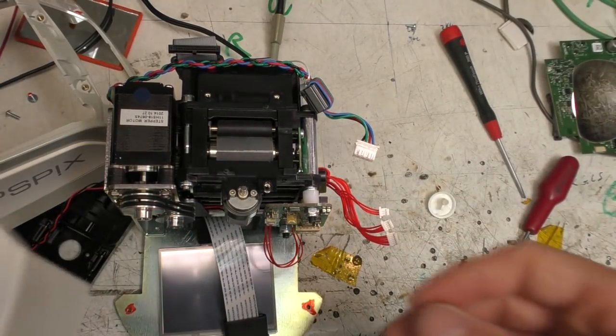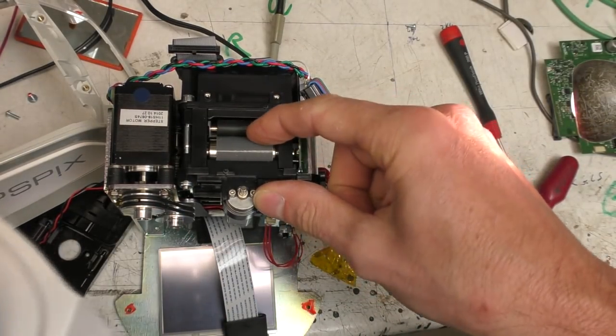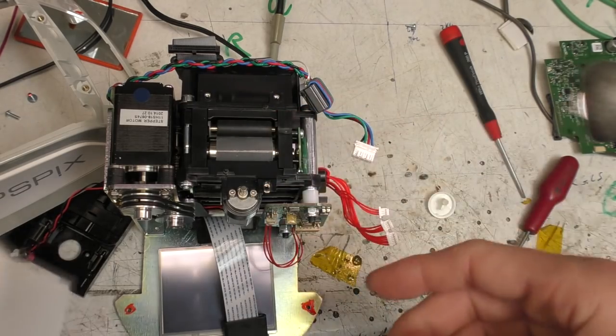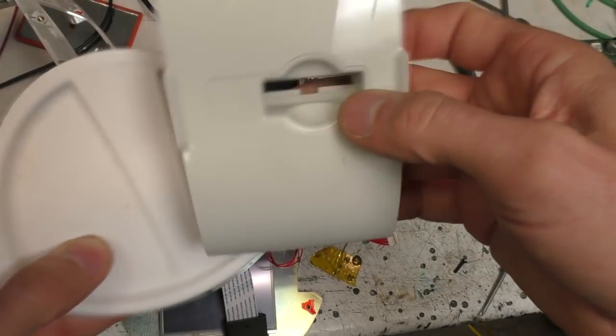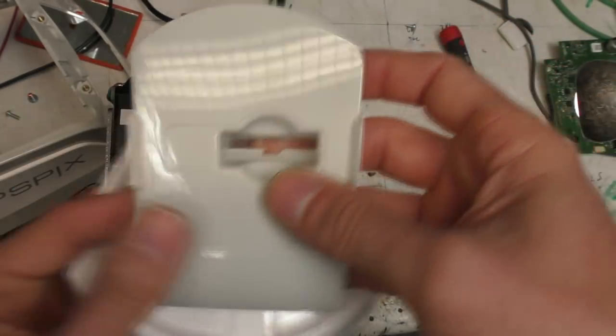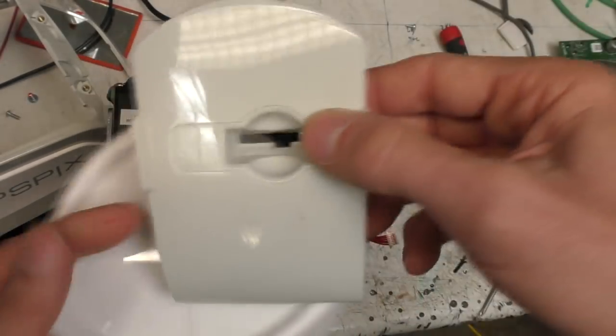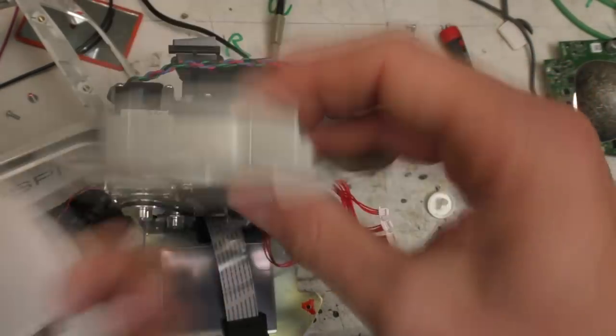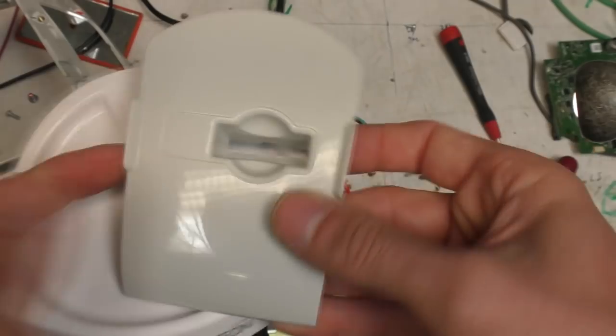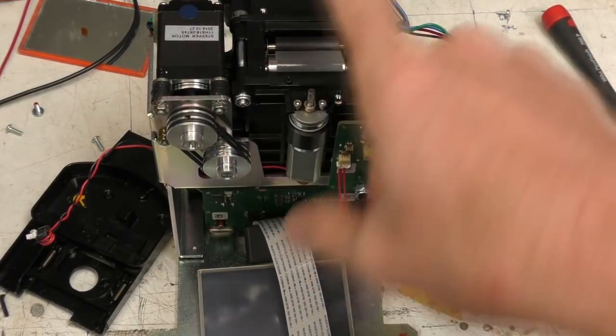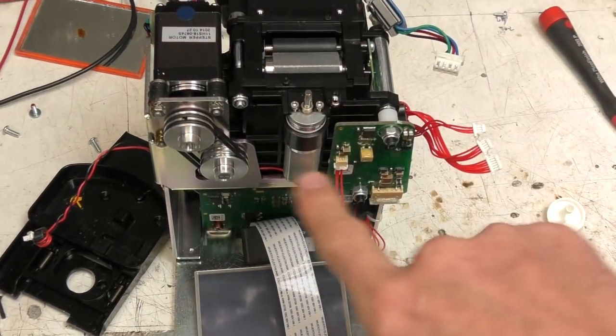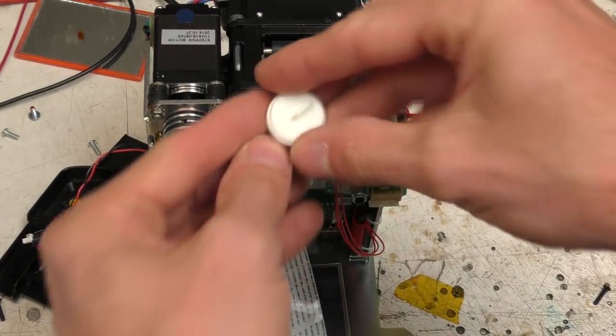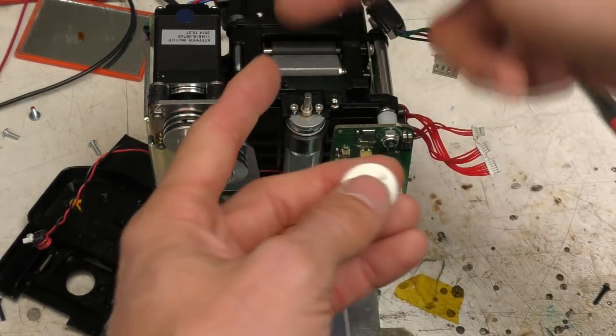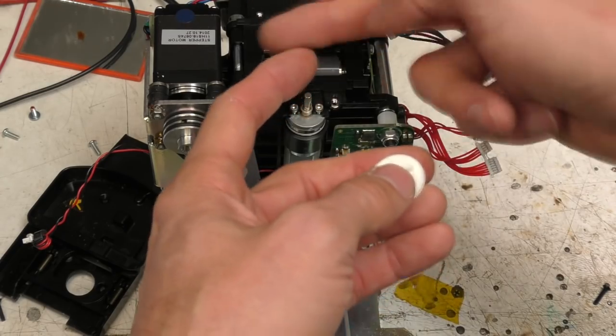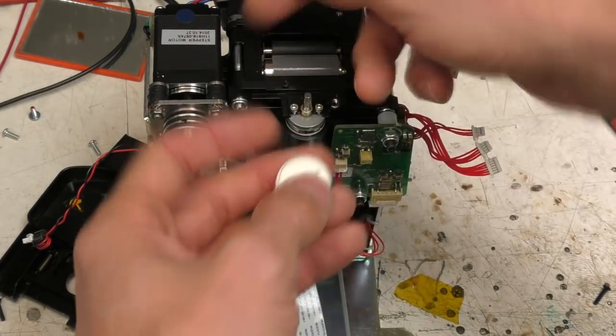Now, I can't find a figure on the image resolution, but it says about 20 lines per millimetre. Also, while I was looking through the manual, I found that the reason for these removable parts is so that they can be sterilised, because these parts come into contact with the plates. So there's the option to remove these so they can go through sterilisation procedures. So you can see this is the stepper motor that moves the plate through. There's also a geared DC motor that operates a cam, which opens and closes the shutter to allow a new plate to drop through, and then closes it back again.